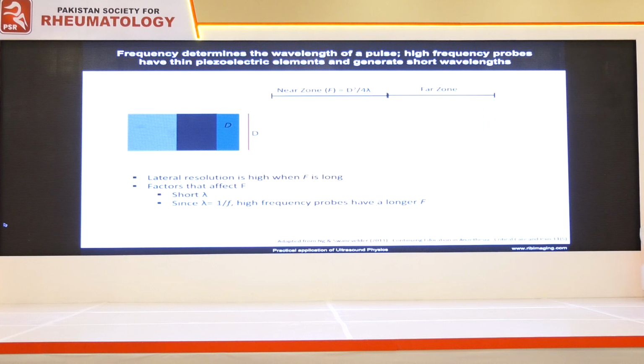I'll stop here for a second to tell you that the reason the curvilinear probes, which are lower frequency, are curved is because the image in a curvilinear probe is produced by the divergent sound wave. It has a very short near zone. The reason you have a curvilinear probe for abdominal imaging is because you need depth, because you're looking at structures that are quite deep down inside the abdomen. So you want a divergent beam for those structures. But for musculoskeletal imaging, and the imaging that you will be doing in rheumatology, you don't want a divergent beam because it doesn't give you very good resolution. It's very good for depth, but you won't be scanning anything beyond 2 to 3, 4 centimeters below the skin, unlike what you need when you're doing abdominal imaging or gynae imaging, for example.